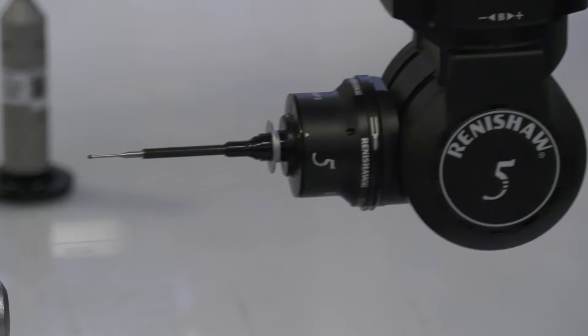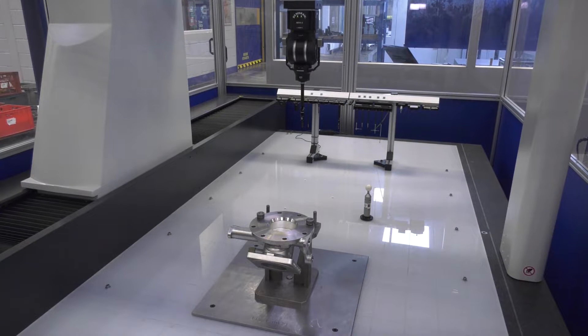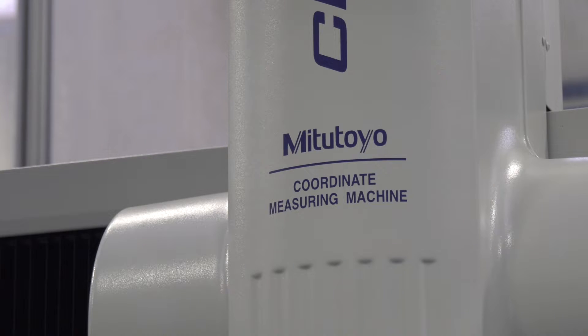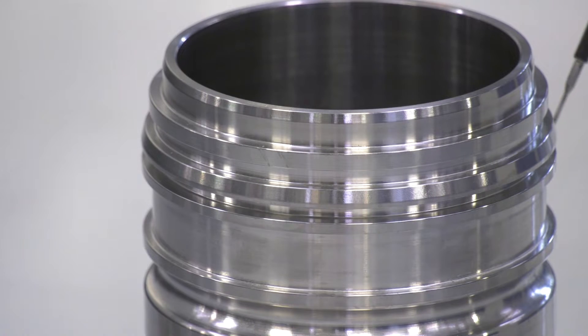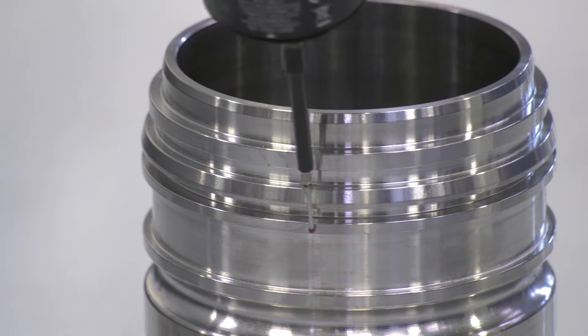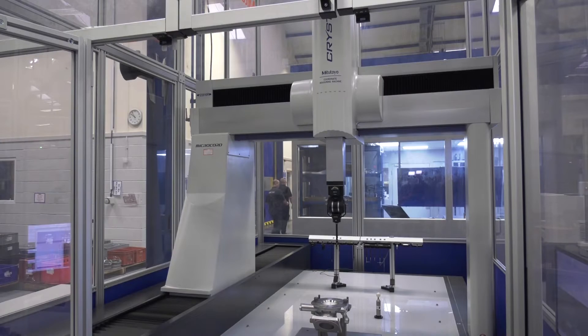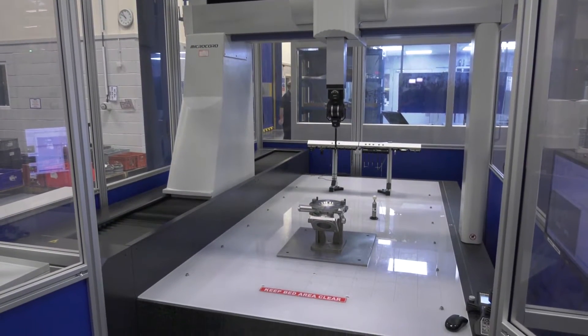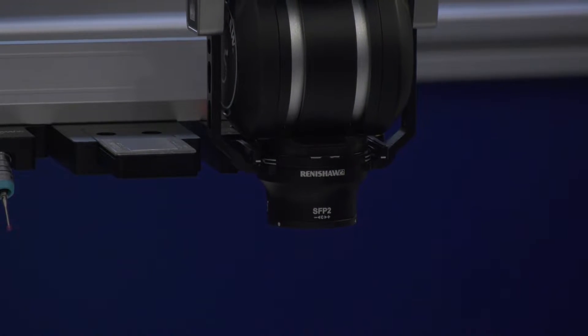A Revo 2 head was supplied by Renishaw on a new CMM. Fort Vale were looking to purchase additional capacity due to company growth. They had an existing touch trigger system but wanted something to match their future growth while minimising footprint. With the Revo system, they achieve the same throughput as two or three CMMs on just one machine, maximising cycle time efficiency.